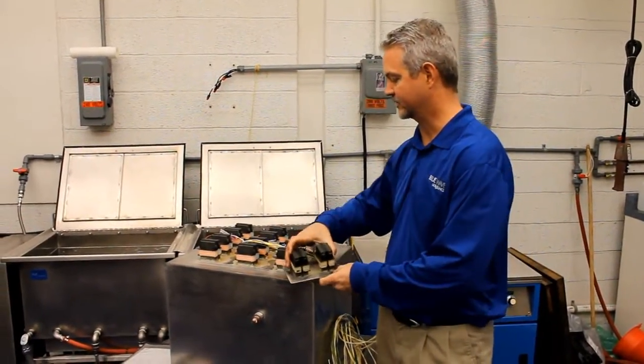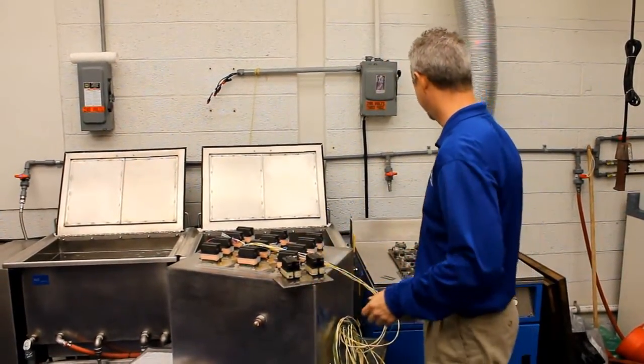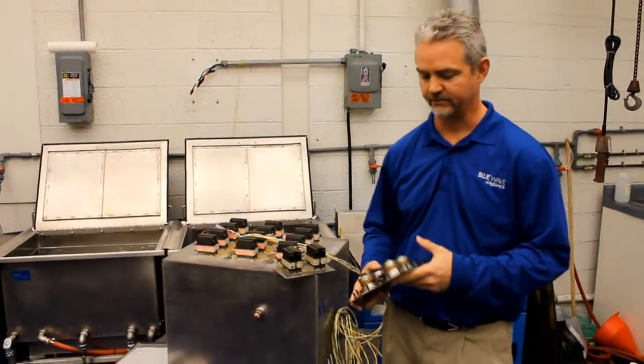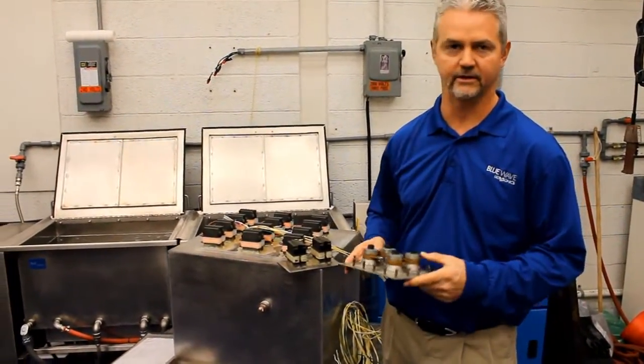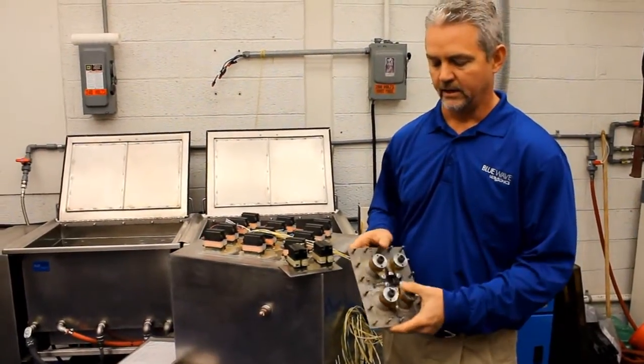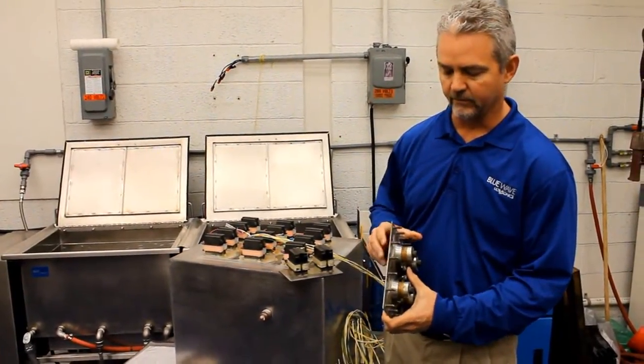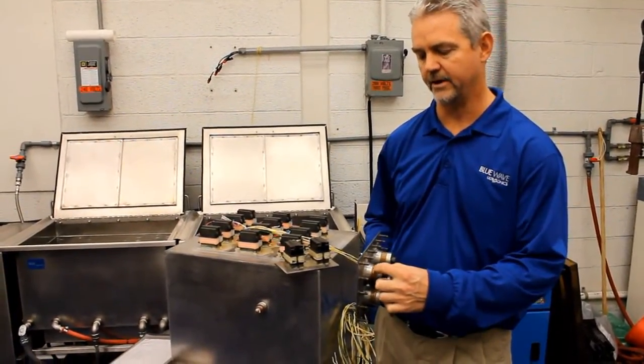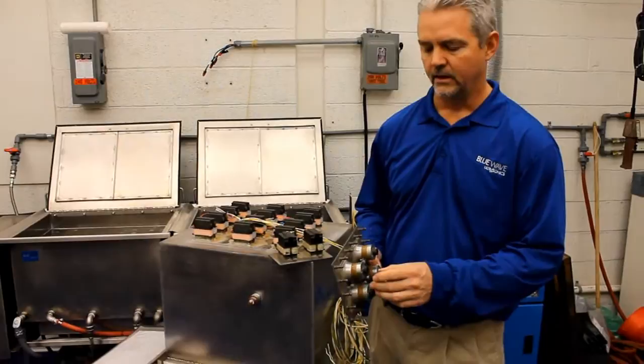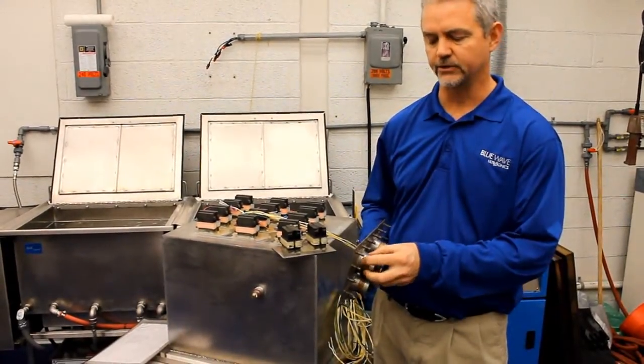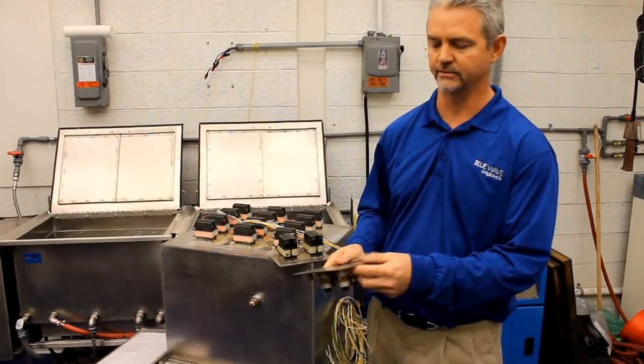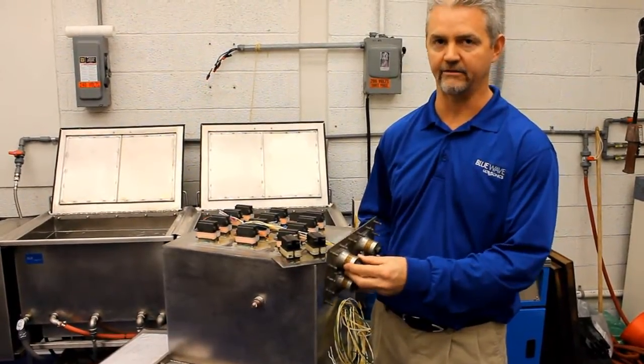Most ultrasonic manufacturers utilize a piezoelectric type transducer. This is what you'll find on most of the companies that are on the internet. The driver for that transducer is this ceramic element right here. When it sees a voltage, it expands or contracts, causing the diaphragm that it's attached to to vibrate at that frequency.